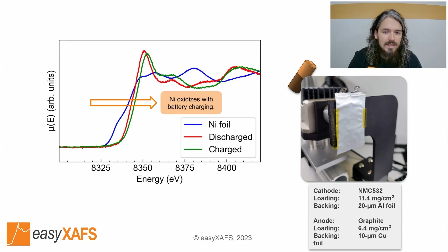So it turns out that the standard battery pouch cell preparation, in terms of mass loadings and metal layer thicknesses, is a good match for transmission mode XAFS. In this plot, you can see very good data quality can be achieved even in just 8 minutes. You can even optimize further. For example, if you just want to get really good quality near the edge and can be a little bit noisier outside of there, you can see that the features are clearly resolved even with only a 2-minute scan. So these shorter measurement times can enable operando measurements of battery cycling even at high charge and discharge rates.